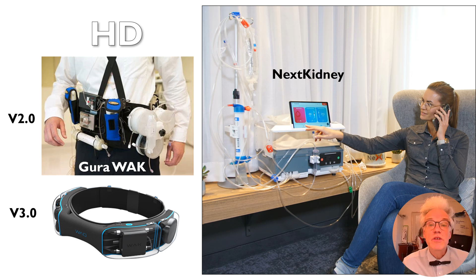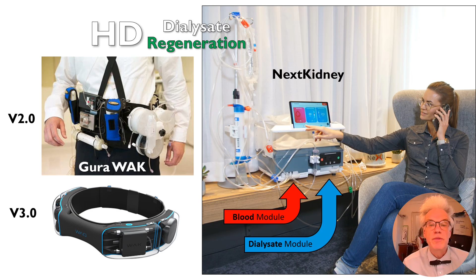Here we see 2 of the dialysate regenerating devices. One is the wearable artificial kidney from Dr. Gura. It's a belt-worn device, but it is quite a bit clumsy when you walk through a door and you may hook on the handle. But version 3 is on its way, which already looks much more sleek. Then the NextKidney there, with the blood module left and the dialysate module right, is being CE marked at this moment. Both use dialysate regeneration and therefore can be so small.